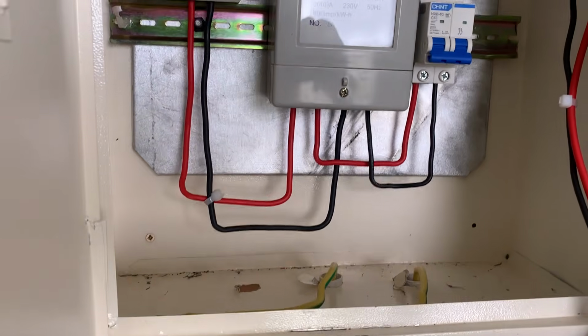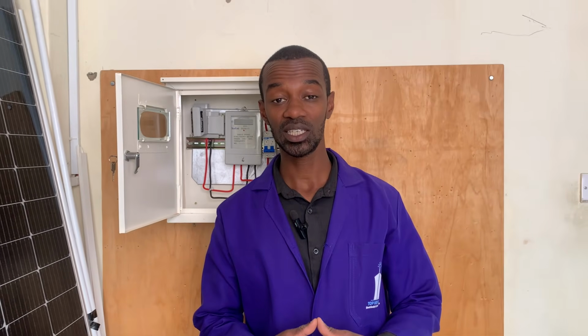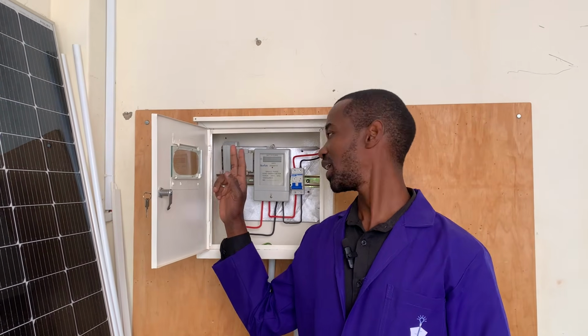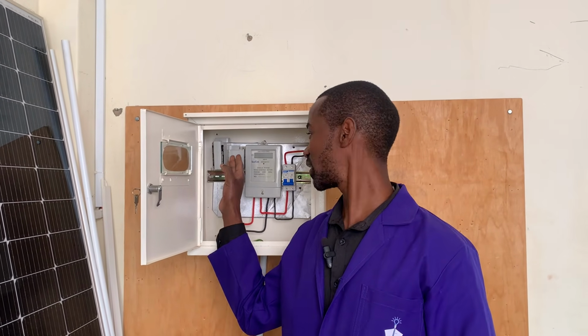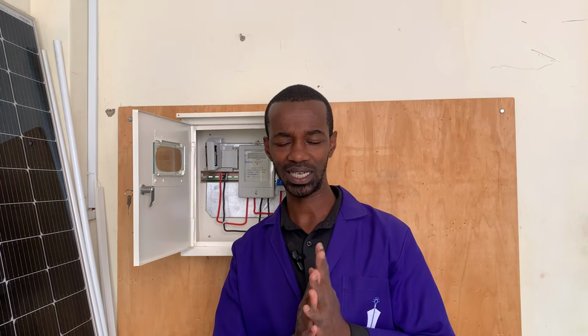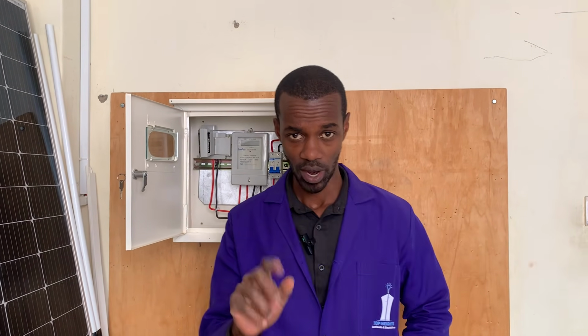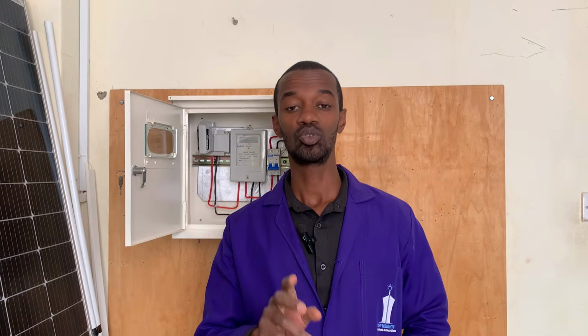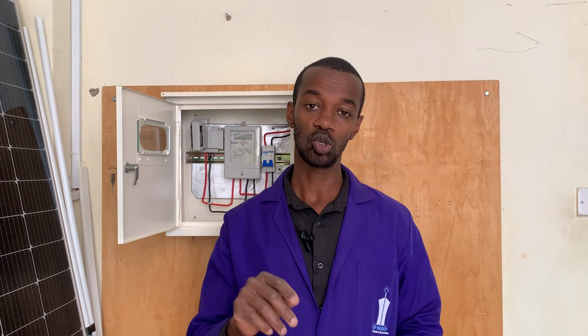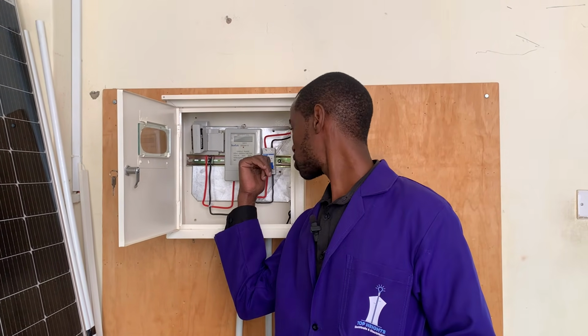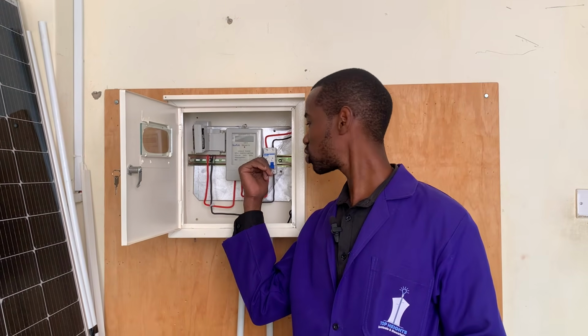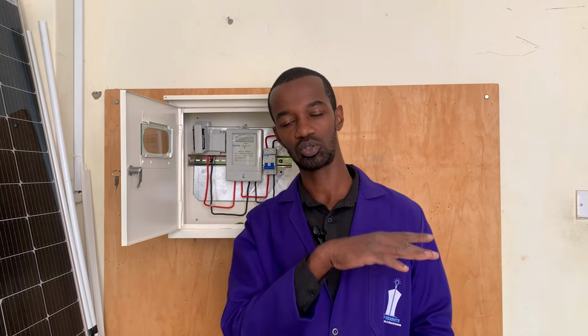I hope you understand, top bosses. We have clearly stated that from the supply at the pole we have two lines only, the line or phase and the neutral. They get to the cutout, and at the cutout we exit with only the phase and the neutral. From there it goes all the way to the meter, then to the output switch or double pole switch right here, and to the consumer unit. The earthing has to be very independent.